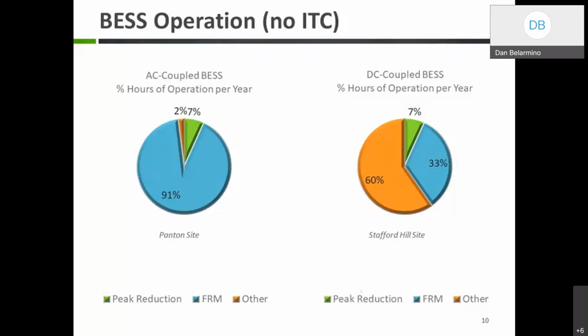On the right is a snapshot of Stafford Hill's operation. Because it's DC coupled, we use the batteries to charge from solar during solar hours, and discharge to about 40 to 50% of state of charge during evening peak hours before putting the batteries in the reg market at night for about 8 hours per day. Any charge left after participating in the reg market, we usually discharge during morning peak hours, then charge from solar again during the day, where the cycle continues.